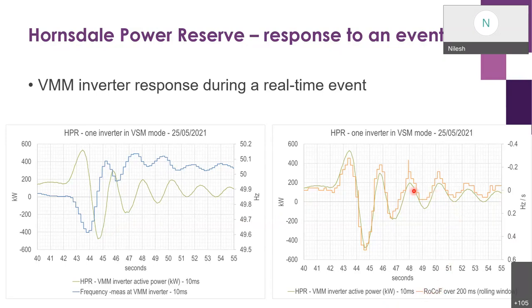And the thing I did was inverse the y-axis. So if you see, the y-axis is not going from bottom to top, but top to bottom. So when the rate of change of frequency is going in an upward direction, it's actually the minus rate of change of frequency. And when the rate of change of frequency is going in a downward direction, it's the positive rate of change of frequency. And I tried to align that with the response in megawatt. And you can see that when the rate of change of frequency is higher, the response is higher or larger.